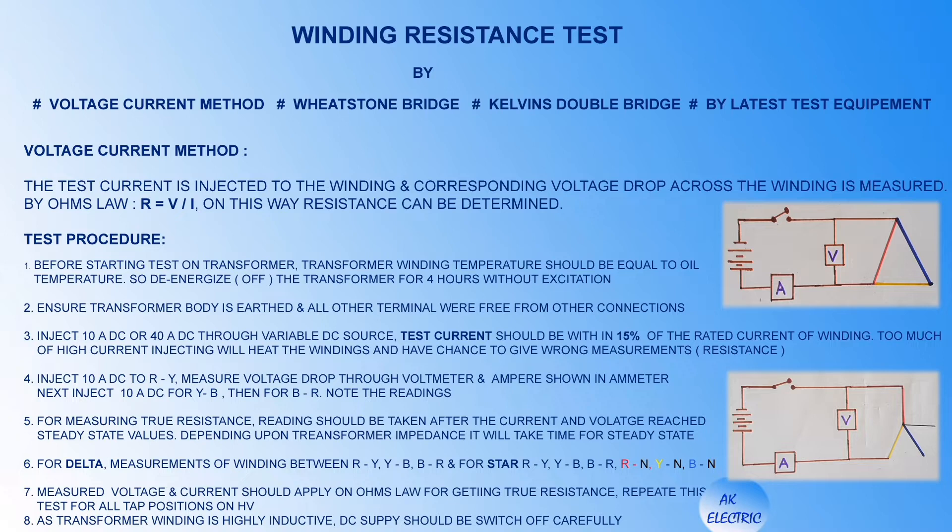For delta connection, measurement is made between R-to-Y, Y-to-B, and B-to-R. For star connection: R-to-Y, Y-to-B, B-to-R, R-to-N, Y-to-N, and B-to-N. Measured voltage and current should be applied to Ohm's law to get the true resistance. Repeat this test for all tap positions on the HV side. As transformer winding is highly inductive, DC supply should be switched off carefully.